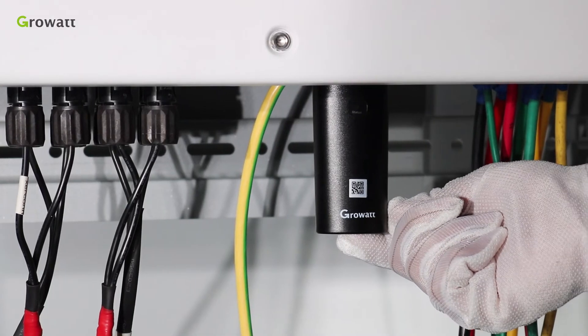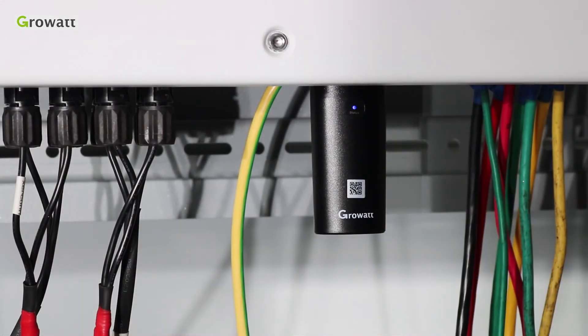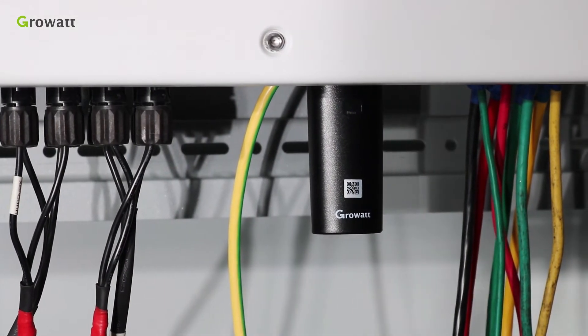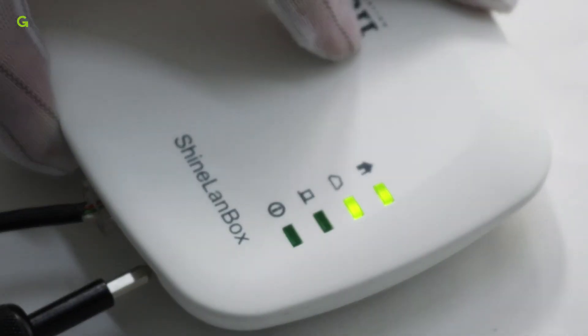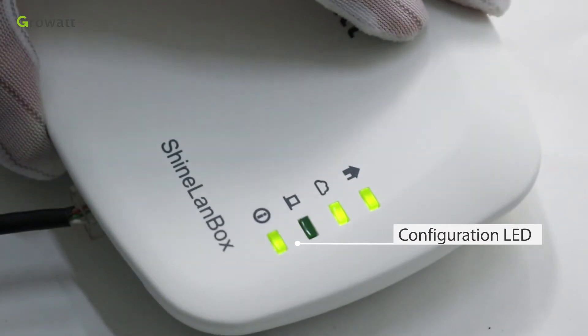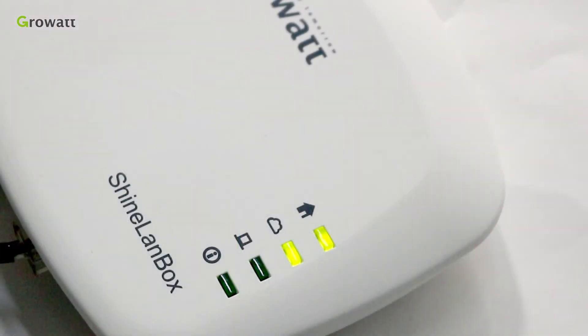At last, pair the RF stick with the ShineLanBox. Short press the button at the bottom of the RF stick. You will find the LED of the RF stick flash fast — it means the RF stick is trying to pair. Then use a screwdriver to short press the pairing button of the ShineLanBox. You will find the pairing LED flash fast, which means the ShineLanBox is trying to pair. When the LED of the RF stick flashes blue slowly and the pairing LED of the ShineLanBox is off, it means pairing succeeded. The device number LED of the ShineLanBox will flash every 2 seconds — how many seconds it flashes indicates how many devices are paired.